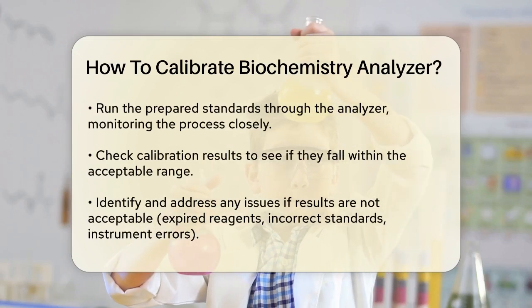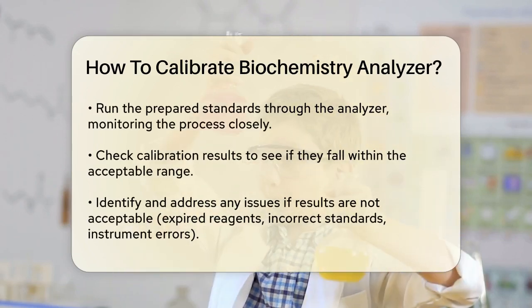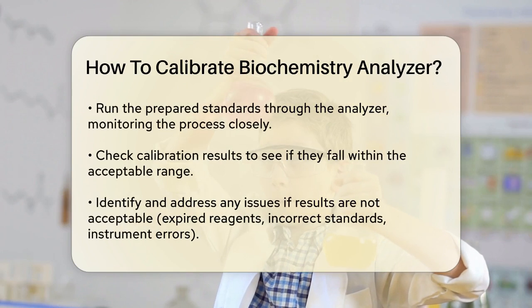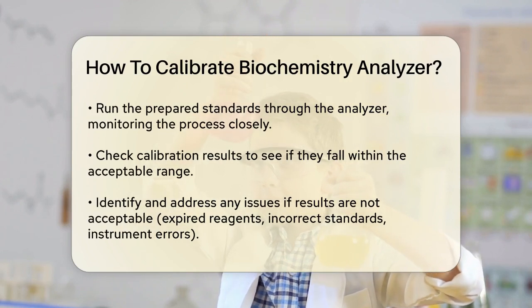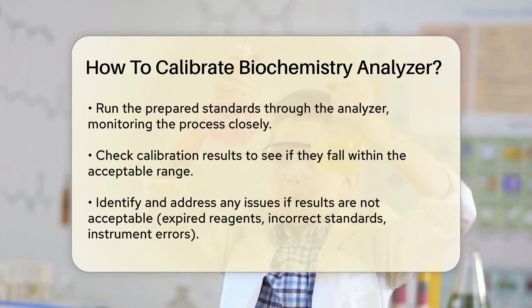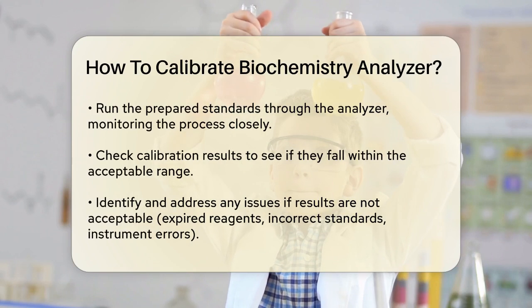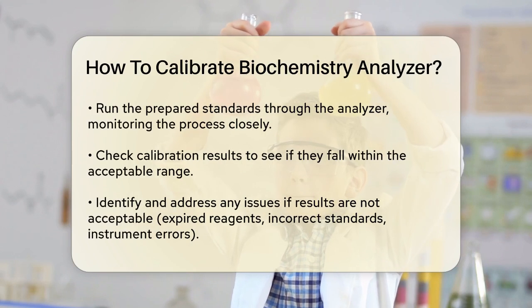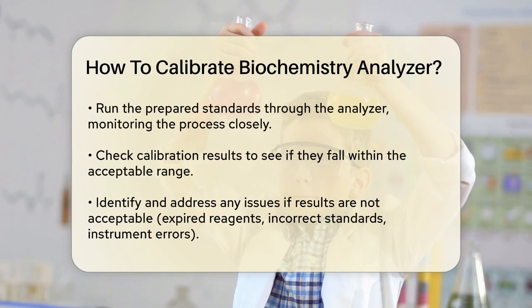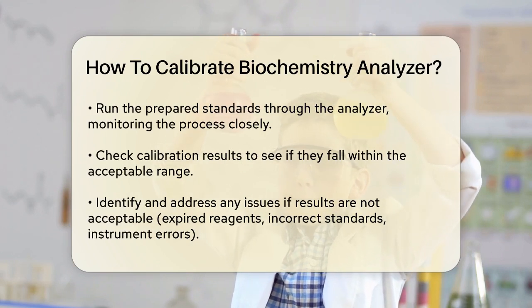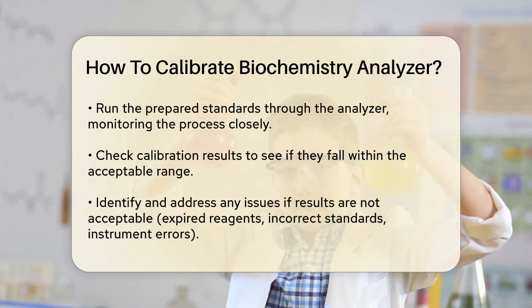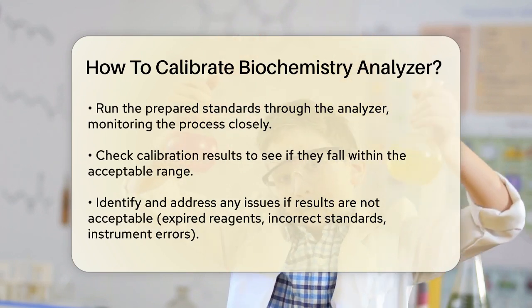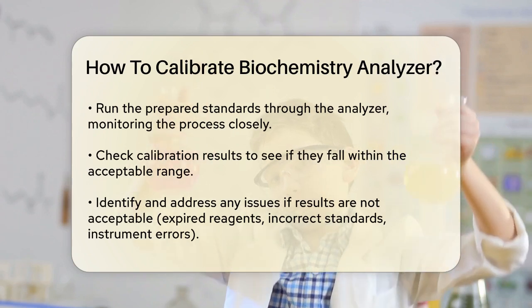Once the standards are ready, run them through the analyzer. Monitor the calibration process closely to ensure it completes without any issues. After the process is finished, check the calibration results to see if they fall within the acceptable range.